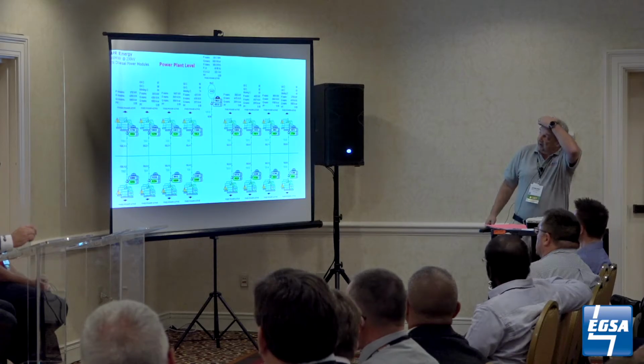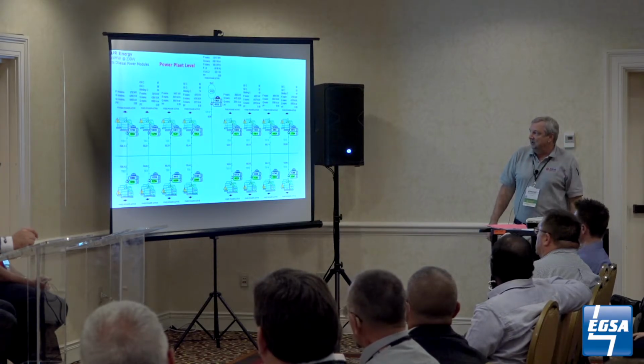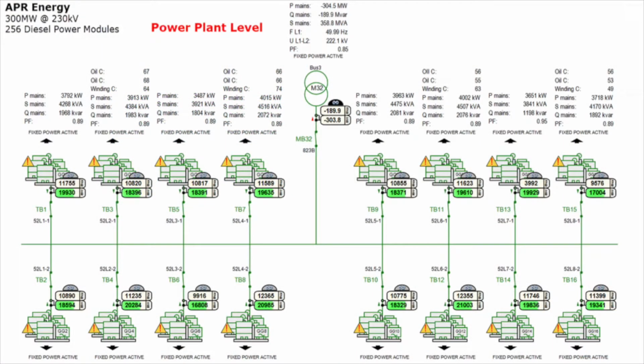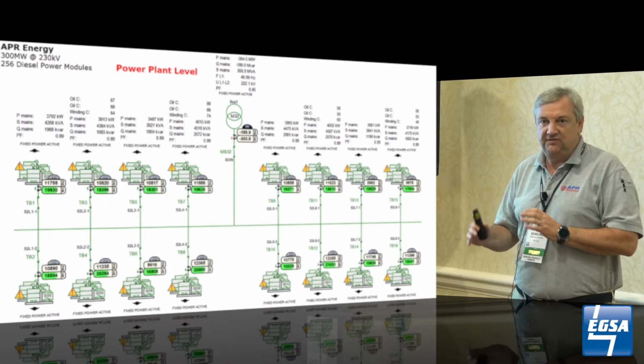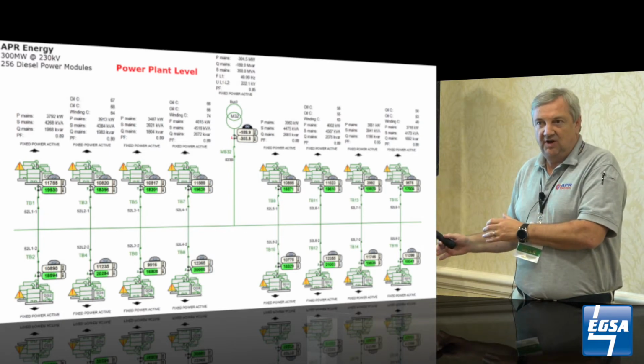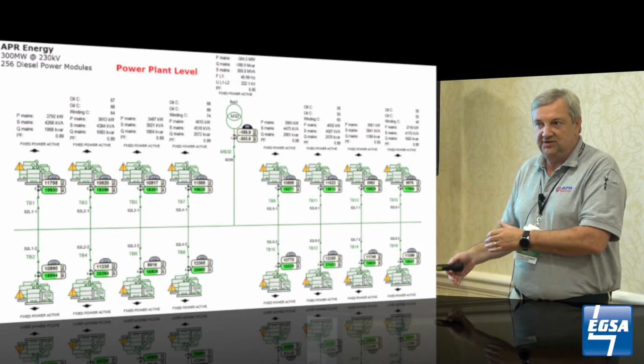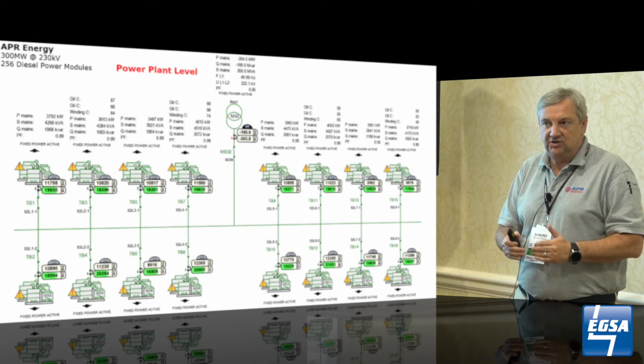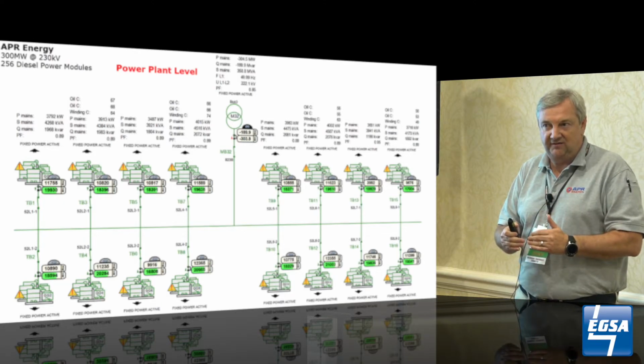This is a heads-up shot of the power plant where we're doing our customer testing in early August. We're up at 300 meg. This was a unique project. We had to hold 0.85 power factor at the interconnect. The contract was very specific. It's not what power factor you're generating at the generators. Regardless of grid conditions, we had to hold a 0.85 power factor.